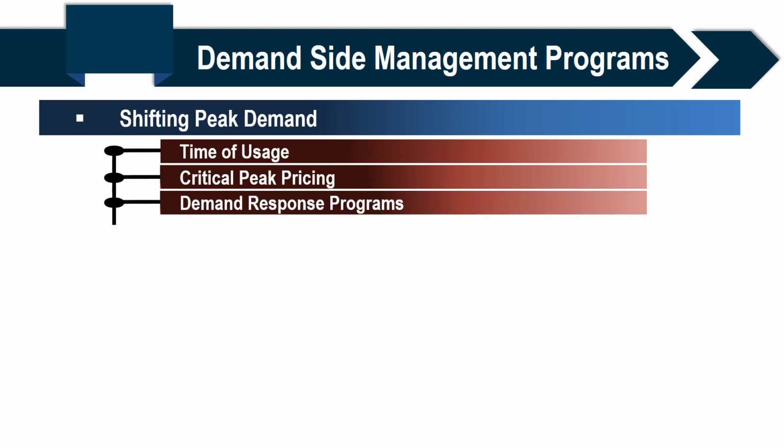There is another method which is used in the industry. It's called demand response program, where users can voluntarily subscribe to DR programs where they allow utilities to control some of their devices for a specific number of periods in a year. For example, if I sign up for a demand response program, utilities can switch off my air conditioner when there is a huge demand, but only for a specific number of times in a year. And depending upon the specific program, utilities provide credit back to the customer.